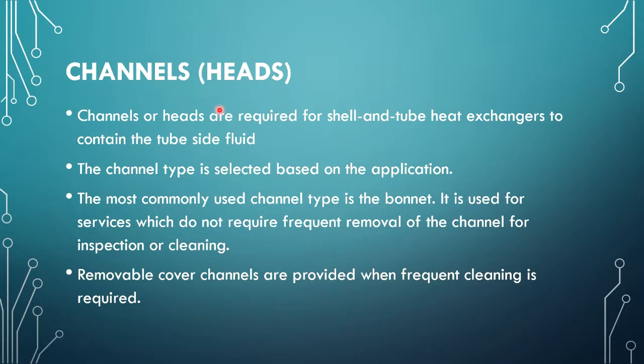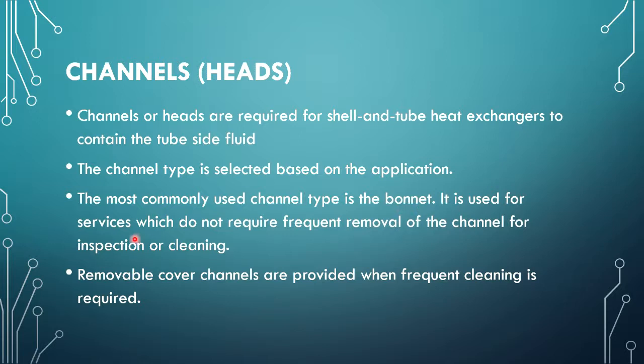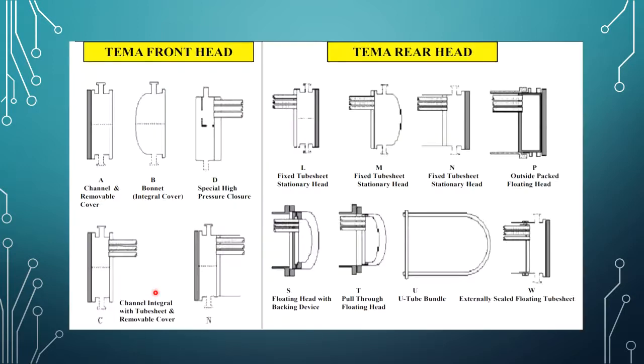The next part is the channel heads. Channels or heads are required in shell and tube heat exchangers to contain the tube side fluid, and the channel type is selected based on the application. The most commonly used channel type is the bonnet type, used for service which does not require frequent removal of the channel for inspection or cleaning. Removable cover channels are provided when frequent cleaning is required.